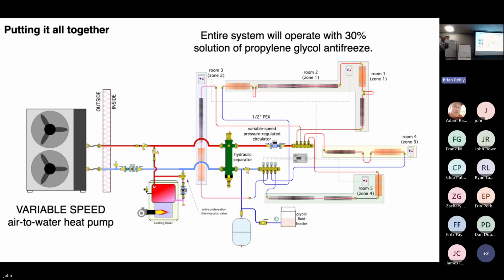Use the idea that load reduction is a possibility, and so is potentially adding heat emitters. And if I'm going to add heat emitters, where am I going to put them? What kind of space requirements? How am I going to reconnect the piping? But ultimately come back to a heat pump and a boiler that are now in parallel. And by the way, remember this, the anti-condensation valve? You're not going to find it on those existing systems.